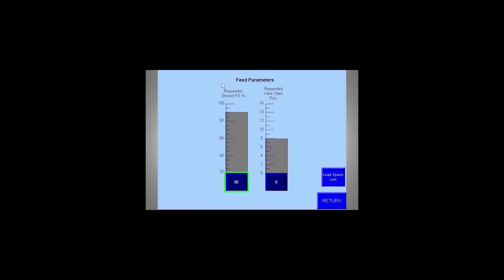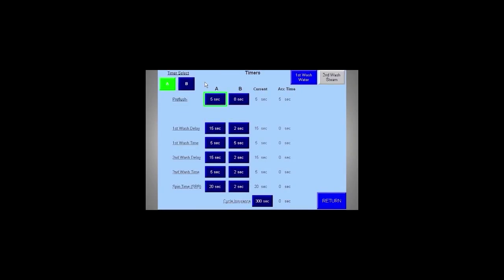The feed parameters screen is used to set the initial valve open position as well as the requested basket fill percentage. The process timer screen allows you to set the times for various portions of the cycle. More importantly, you can set two independent sets of timers to quickly switch between two massecuite types, as well as select water or steam for each wash cycle.